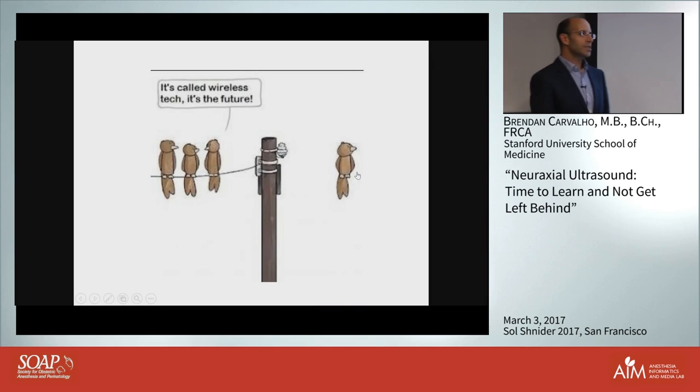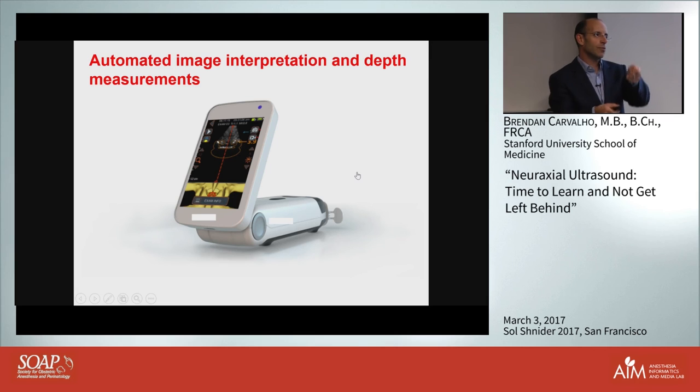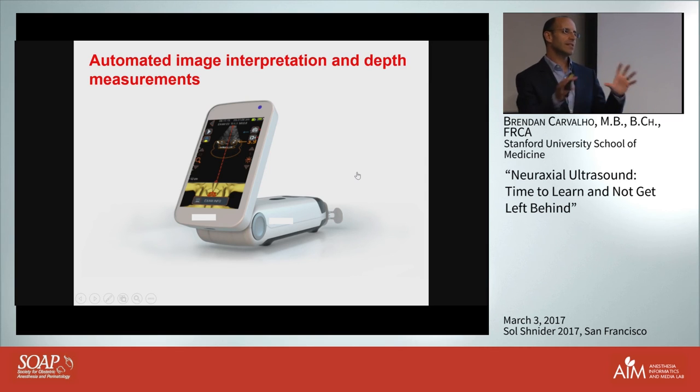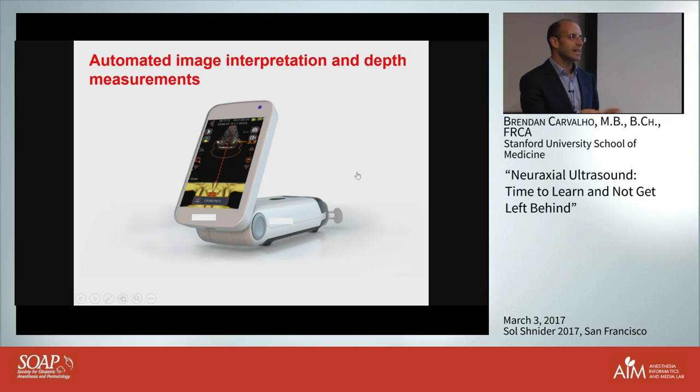Where are we heading in the future? Some of what I'll discuss is already here. The Accuro device by Rivanna - and I acknowledge I received research funding from them - creates pattern recognition and has software that tells you where it thinks the interspace is and gives you a depth reading automatically, for example 3.9 centimeters. We've recently studied it - it's within 7 millimeters of actual needle placement and within 3 millimeters compared to a more sophisticated console ultrasound. It may help individuals who feel overwhelmed by pattern recognition, but my concern is performance in the morbidly obese patient where visibility is most challenging and where it hasn't yet been adequately studied.